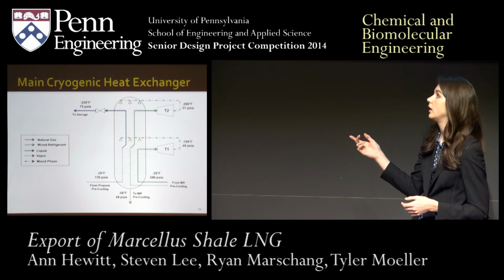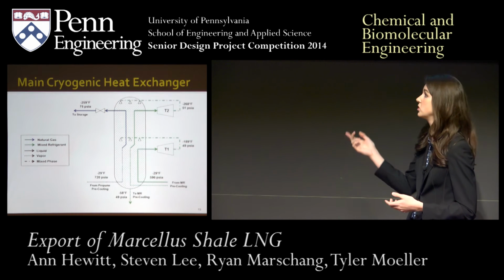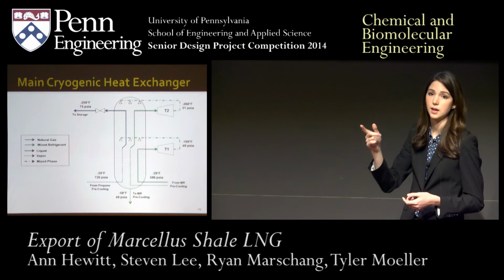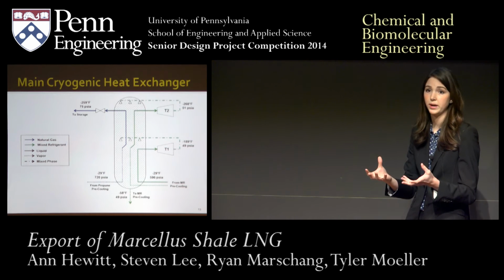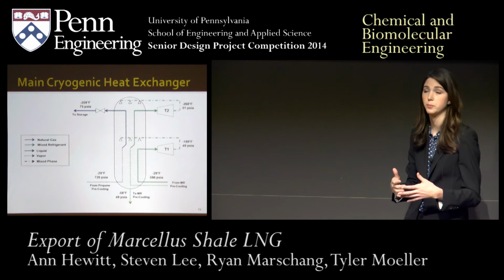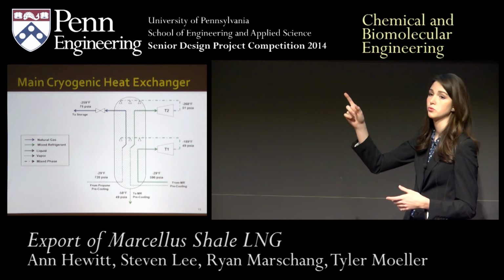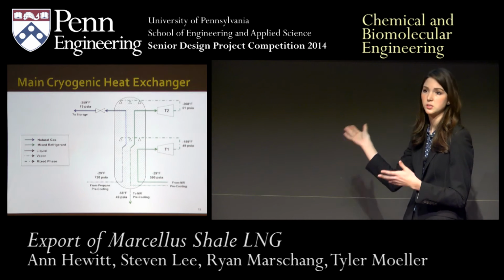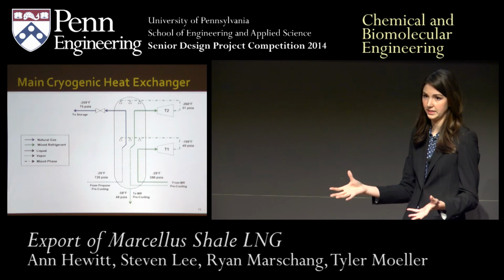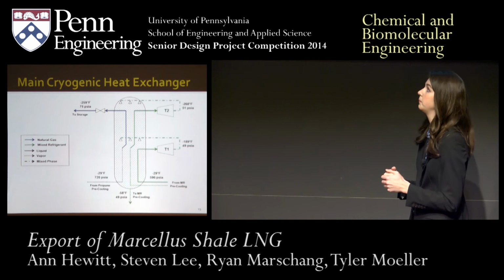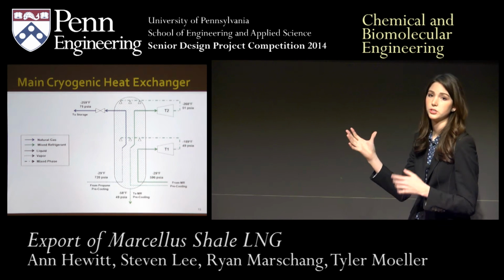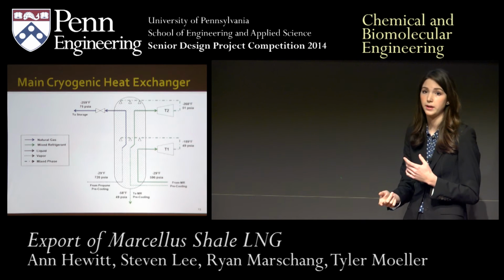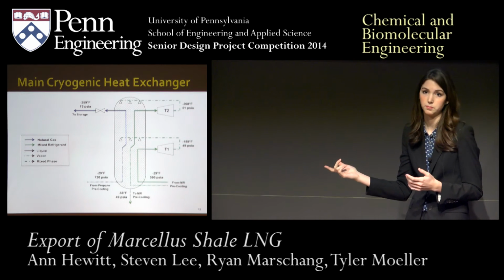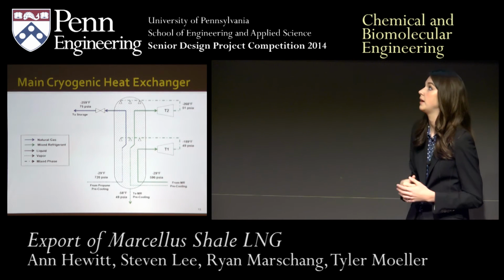If we follow our vaporized mixed refrigerant stream, the dotted green line, it rises up through our warm bundle. Because of that spray, it's cooled and phase changes about halfway up our exchanger, then continues to rise up through the top. Like the first stream, it's expanded through a turbine, cooled, and then sprayed down over the tubes rising up through. All of this mixed refrigerant collects and leaves through the bottom, back to the mixed refrigerant pre-cooling process we just looked at.